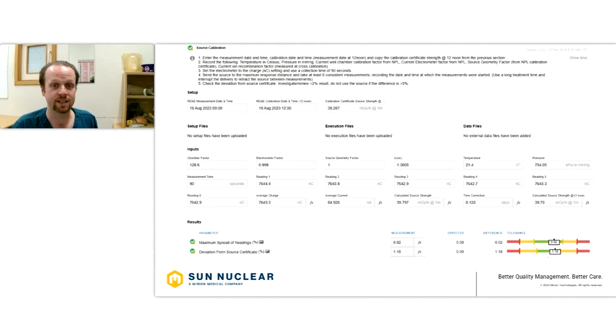Additionally, we can use this template to embed complex calculations, such as this one that's used for source calibration. It allows space for electrometer and chamber factors to be input, as well as atmospheric and ion recombination corrections.